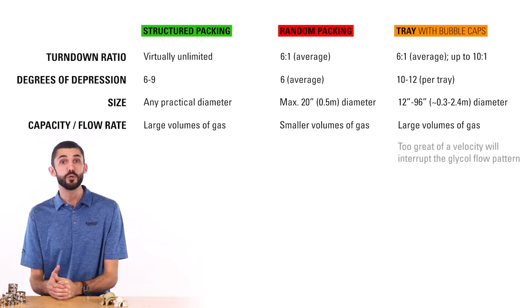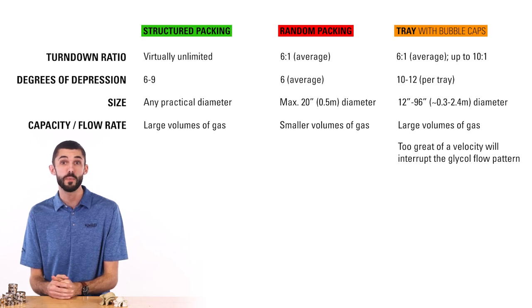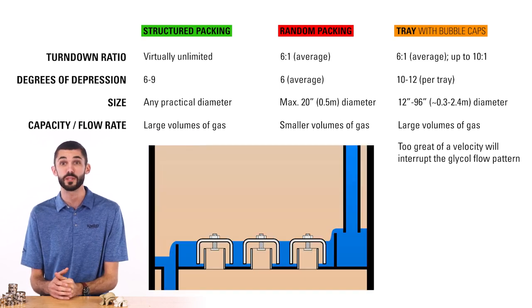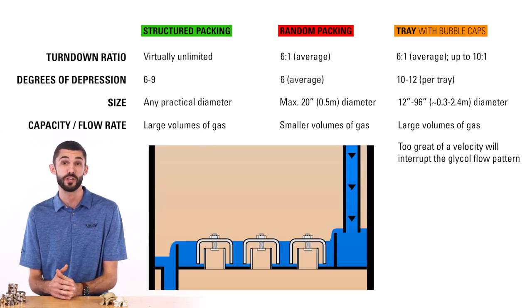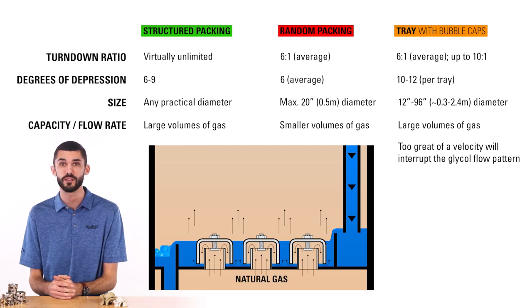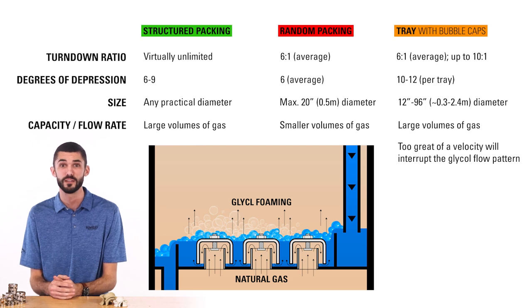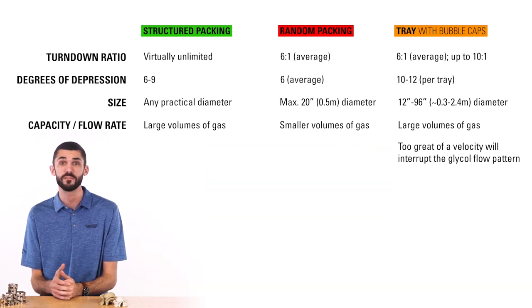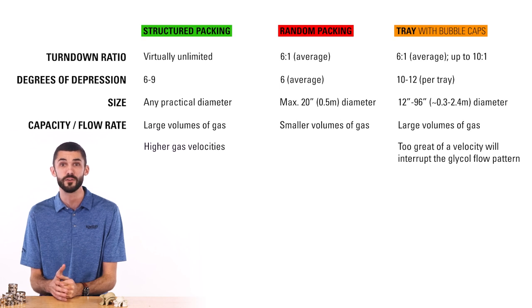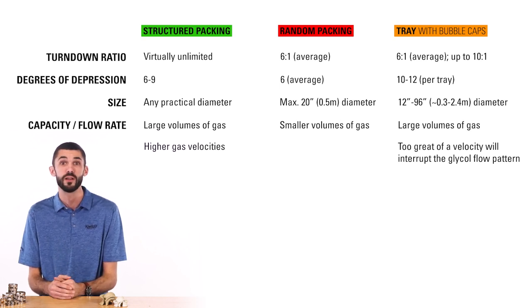In a tray tower, greater gas velocity will interrupt the glycol flow pattern and break the liquid seals at the points where the tray downcomers meet the trays. This results in glycol being swept out of the tower with the gas. Because of the design of the structured packing, gas velocities can be higher than in tray towers, because the glycol will not be swept out of the tower by high gas velocities.